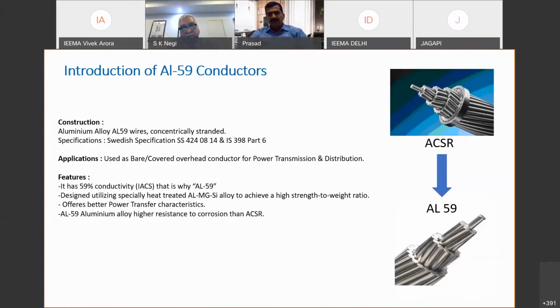We would like to have a look at the features of these conductors. It has 59% conductivity, and that's why it is AL59. It is basically an aluminum, magnesium, silicon alloy only. However, with some specialized heat treatments, it has the best strength to weight ratio compared to ACSR conductors. Of course, due to better conductivity, it offers excellent power transmission characteristics.